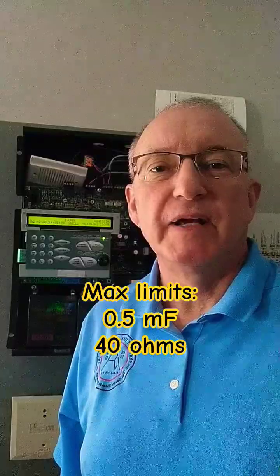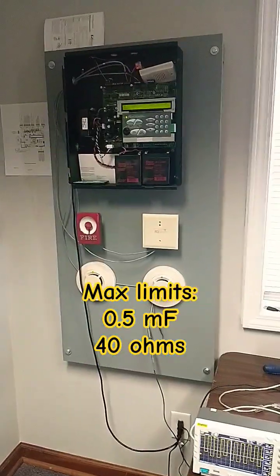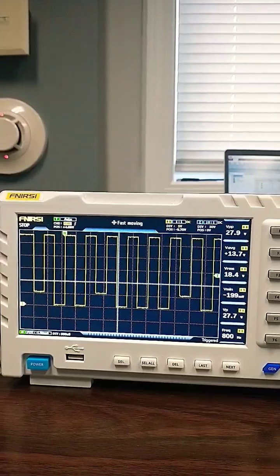Let's connect an oscilloscope to the 7100 system behind me and see what the SLC signals look like. We have four devices connected to the system and this is what the oscilloscope signal looks like in normal condition.